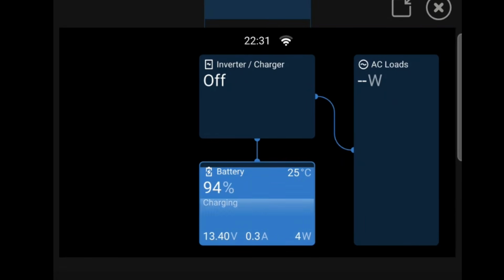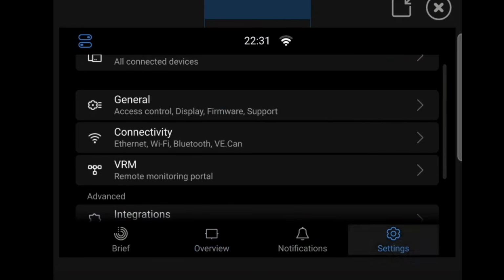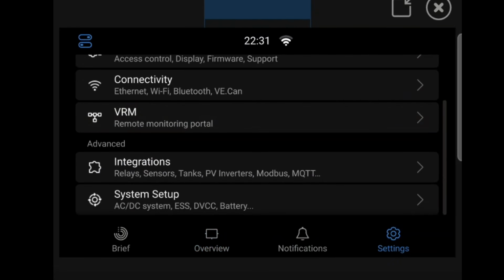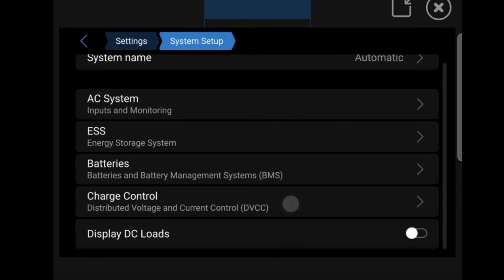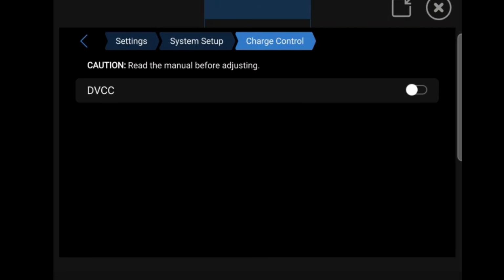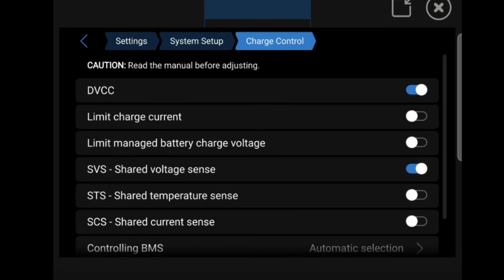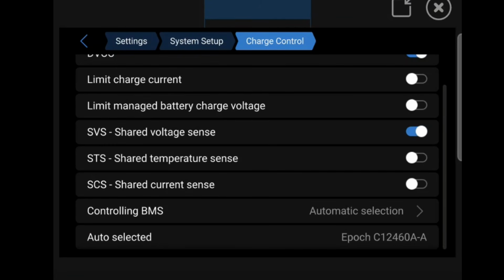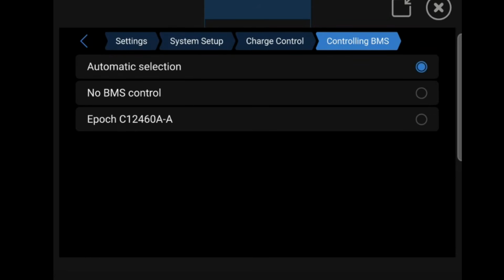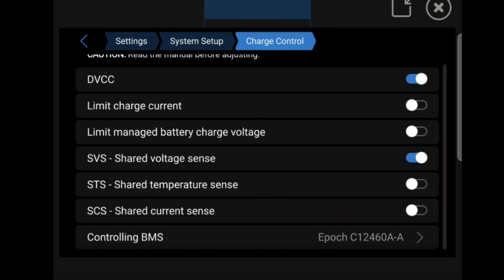Next we're going to enable DVCC and set the Epoch BMS as the controlling BMS. Tap the screen, go to settings, system setup, charge control, and there's DVCC, currently turned off. Toggle DVCC on - that enables a host of other items. At the bottom it says controlling BMS, currently on automatic selection, but we want to set that to Epoch as the controlling BMS. Also make sure SVS, shared voltage sense, is on. The rest can stay off - we don't need to do anything else here.